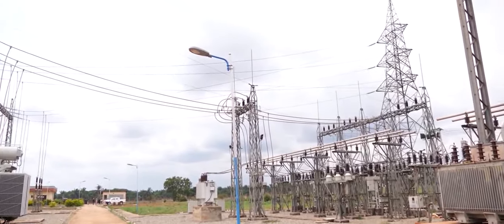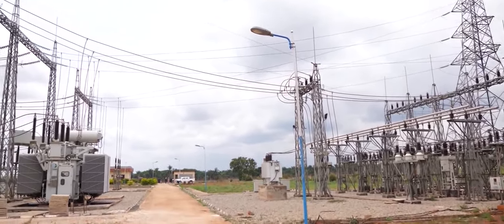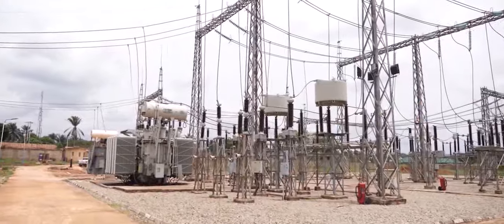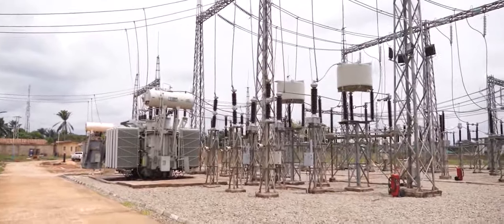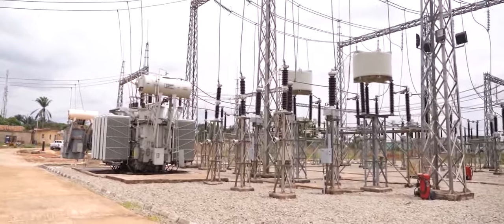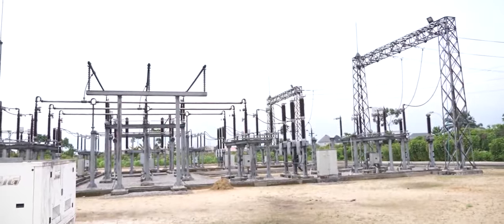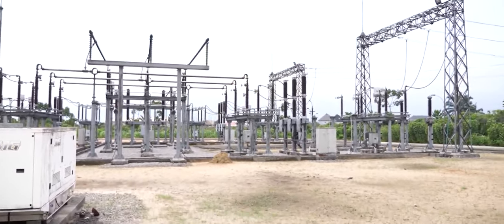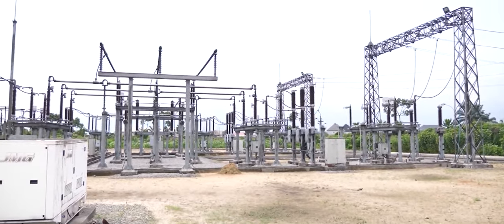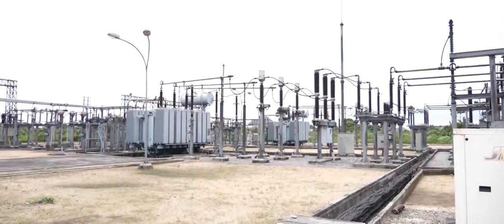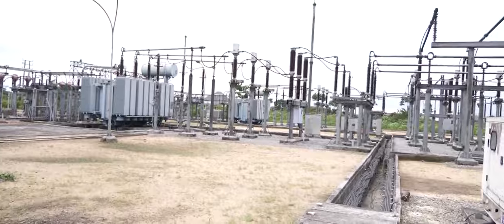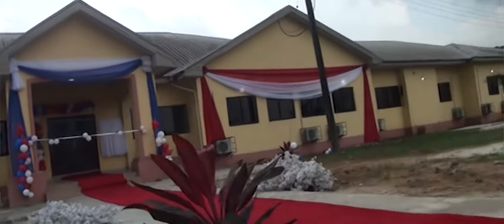At the 132/33 kilovolts Nsukka transmission substation in Enugu State, TCN also installed a 30 MVA power transformer to double the substation's capacity. TCN also added a brand new 100 MVA power transformer at the 132 kilovolts Port Harcourt main transmission substation and also commissioned the Port Harcourt regional office building.